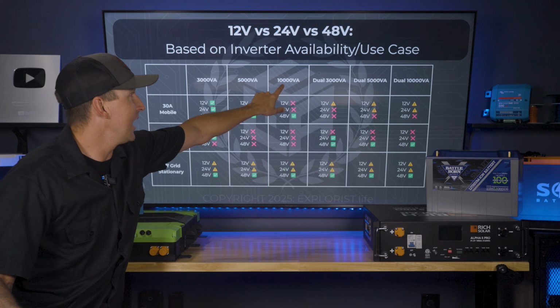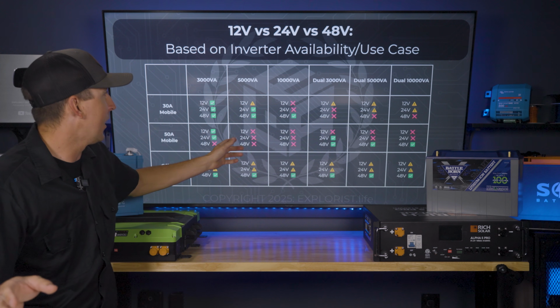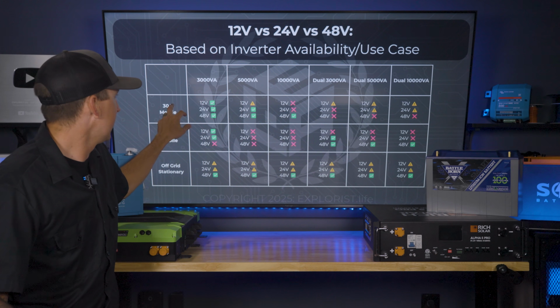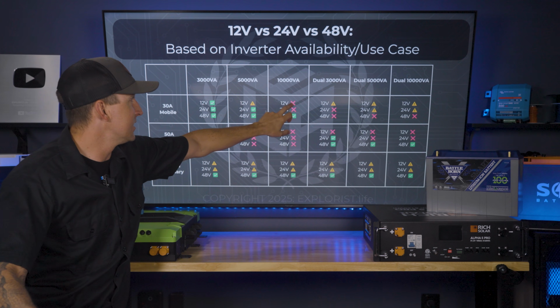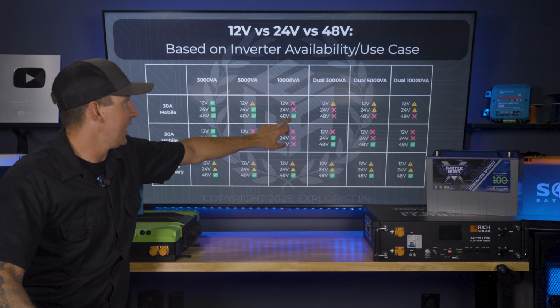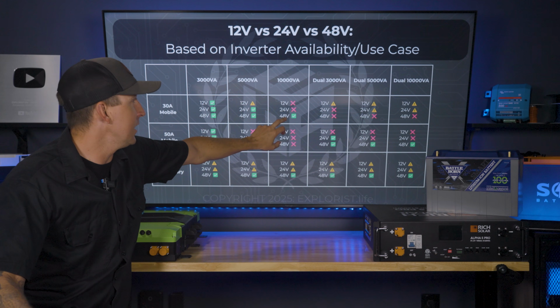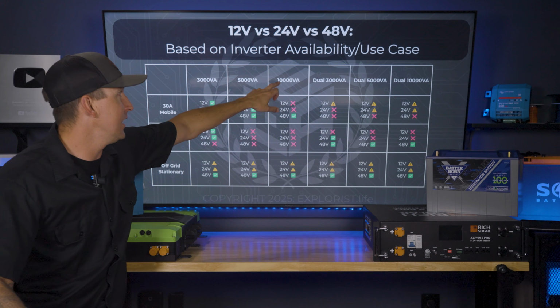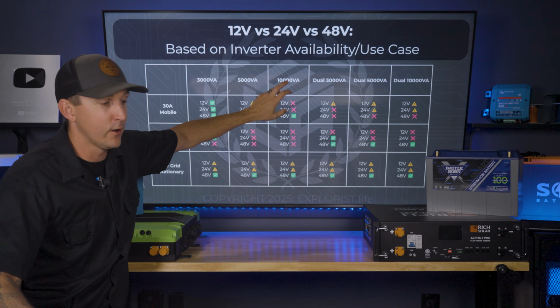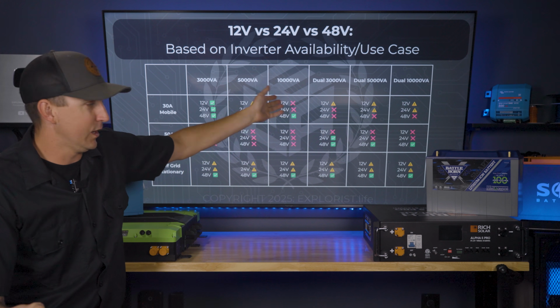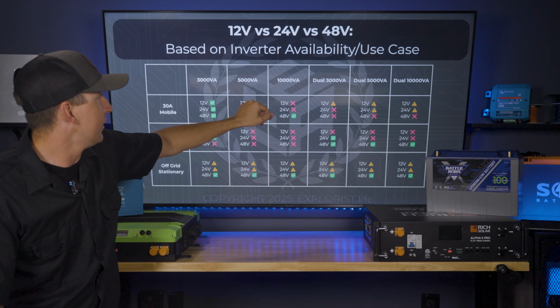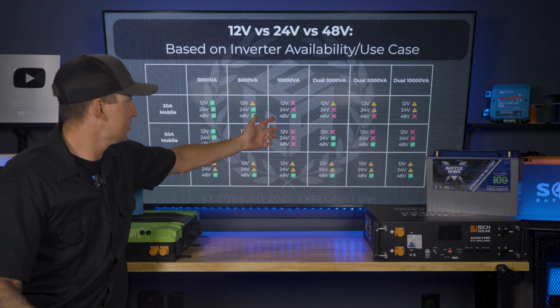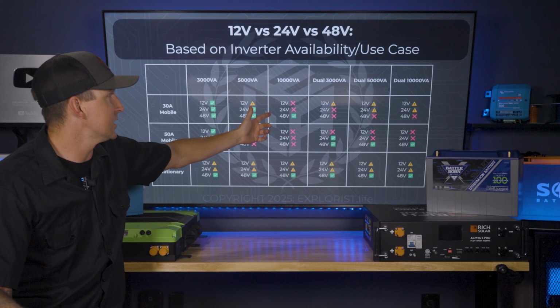Now, if you had a 10 kVA system, you'd have quite a bit of power needed. Same concept, but the 12 or 24 volt version doesn't exist as an actual component - only the 48 volt version does. So if you needed this much inverting power to power nearly 10,000 watts of devices, you only have the option of doing 48 volt systems.